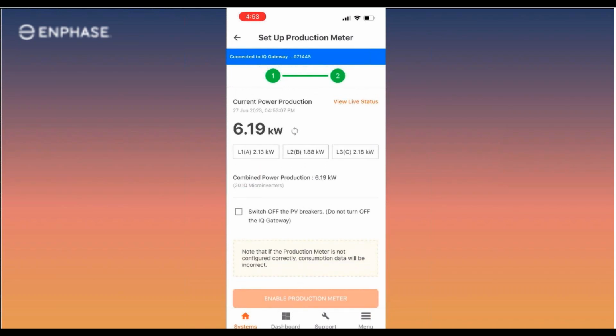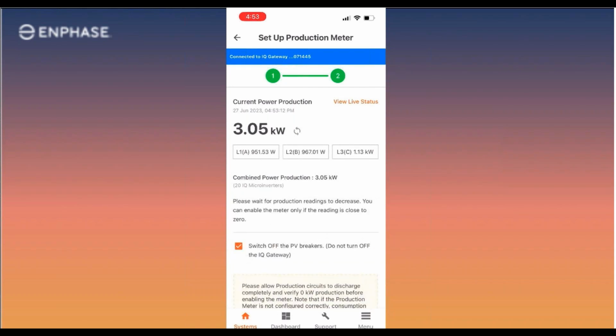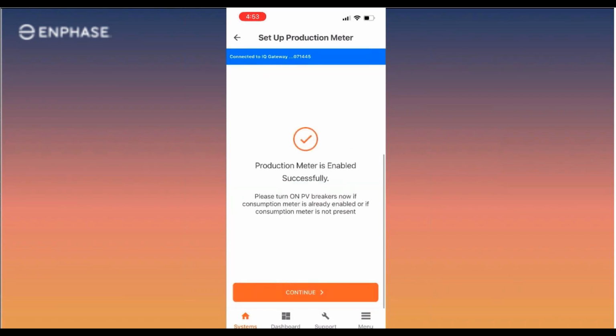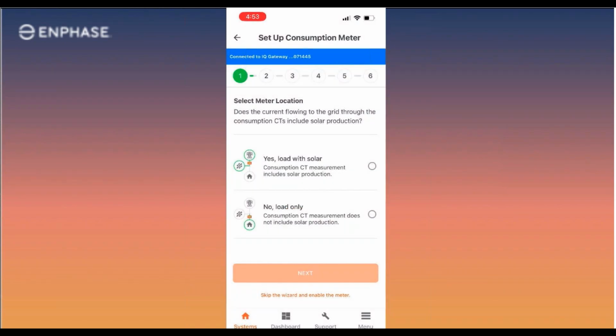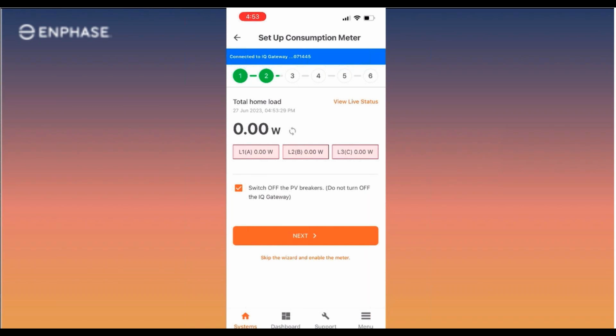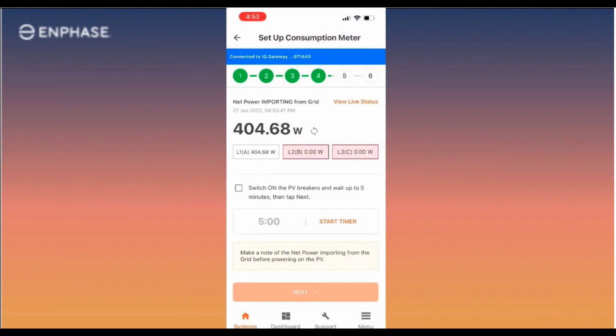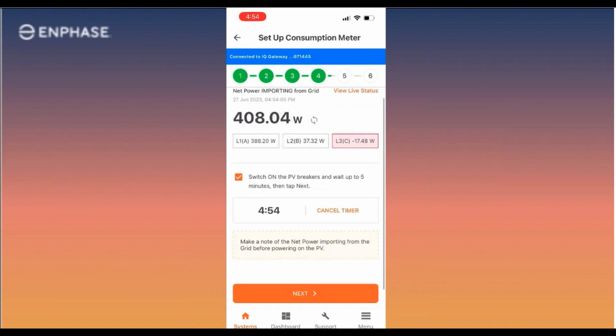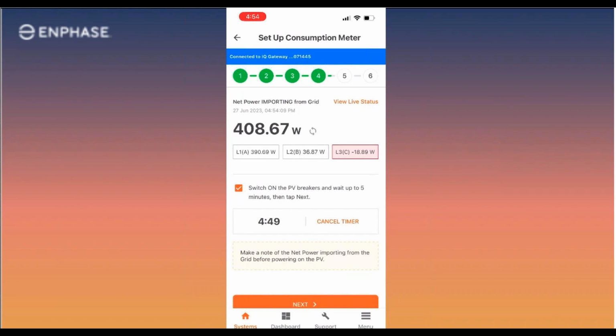If you haven't used the Installer Toolkit app before, it walks you through all the steps and won't let you go to the next step until the previous one is completed and correct. So there's no chance you can set up or commission the system incorrectly. If you get an error or a message you're not sure about, the app will walk you through troubleshooting. As mentioned, it has the CT wizard built right in, so if you're having issues with CTs, maybe they weren't installed correctly, it'll give you troubleshooting techniques to figure out the issue.